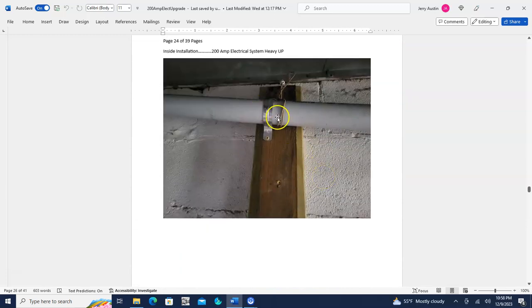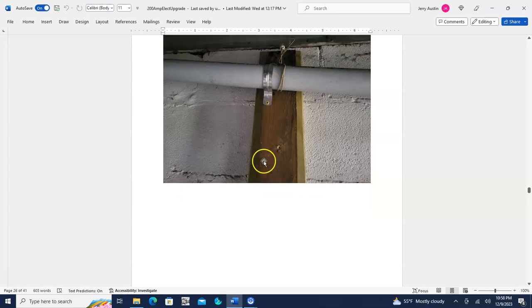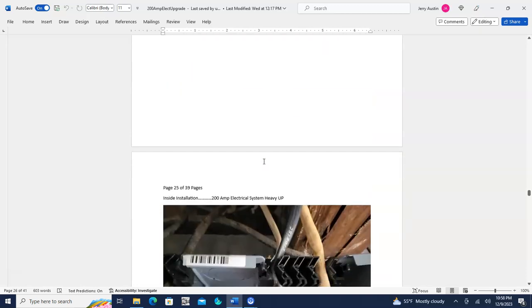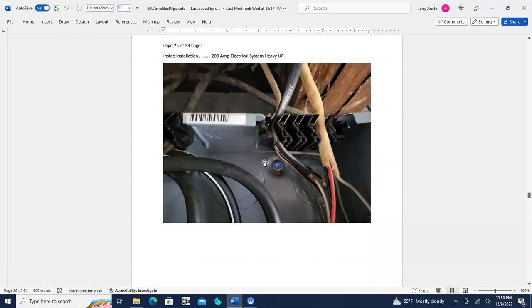And this PVC pipe has to be anchored to something, so it's anchored there to keep it from sagging. On this particular box, you have these wire feed throughs up at the top of the box, which is really handy. You don't have to do the knockouts on the side and then put little wire clamps in with those screw holders on them. So this is really handy the way this new circuit breaker box came.